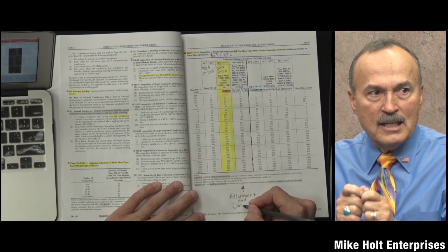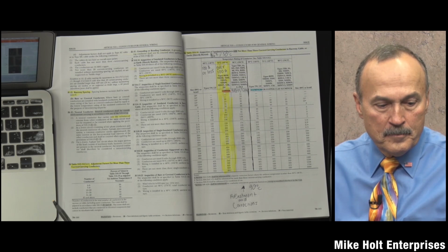It's in, I go to table 310.16. I know I use the 90-degree C. I make the note, I make that reference, and I can go back to it, and I can find it. It's when you have to prove something to somebody, and it's something that you don't use often, it's hard. Boyd: Like I say, the majority of the time that I mention the 90-degree column is to say that the only reason it's there is so you know what to look for when you go to temperature and bundling adjustments.